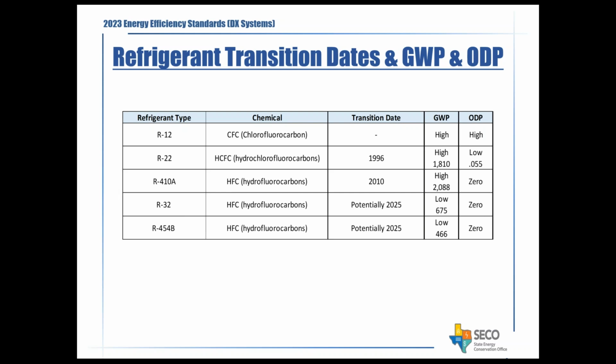The key thing to keep in mind about this new standard in 2025 is that the GWP factor needs to be lower than 750. So going forward, you all need to be aware of that and start planning, from maintenance and construction standards and so forth. You at least need to be aware of these things. This was just a very simplistic comparison.